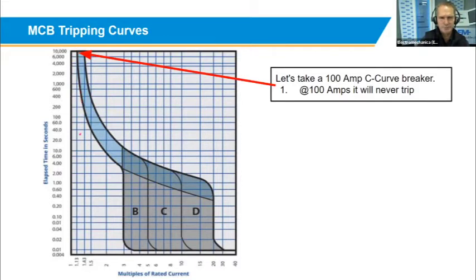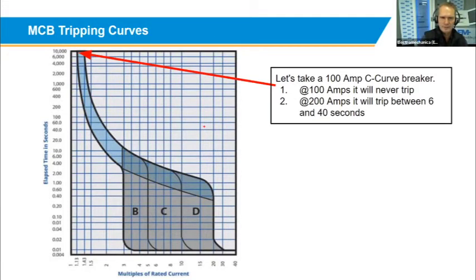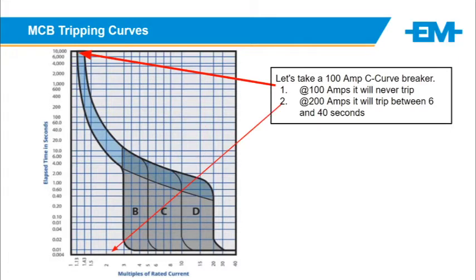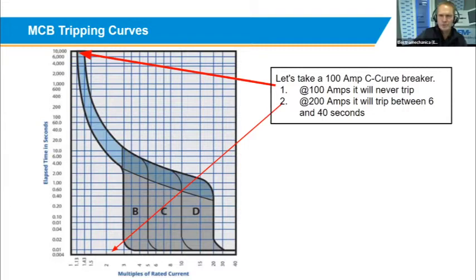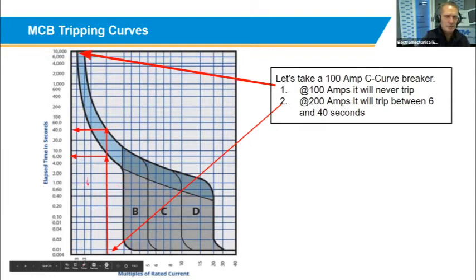So if you then take that same circuit breaker and you put 200 amps through it, what will happen is you can go to the 200 percent mark. You can draw a line upwards to where it touches the curve the first time. You draw another one up to where it touches your curve the second time. Go to the left from both these points where it touches your curve, and you will now see that a C curve 100 amp circuit breaker running at 200 amps will only trip between 6 seconds and 40 seconds.